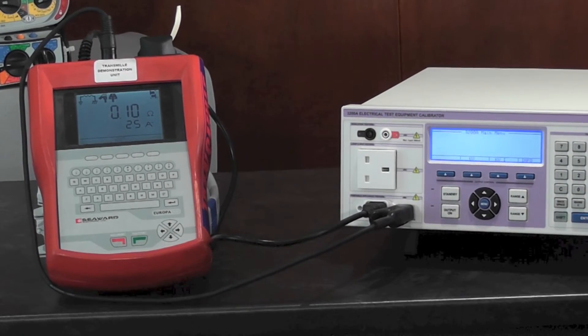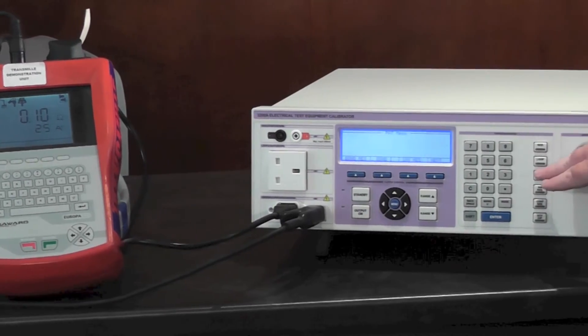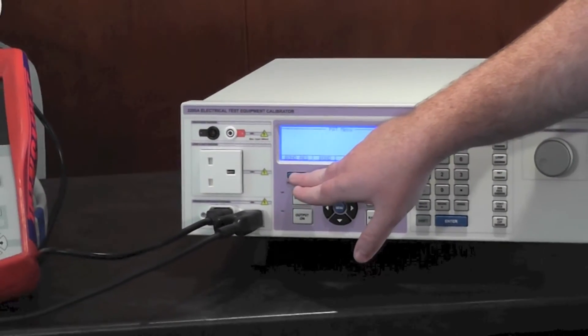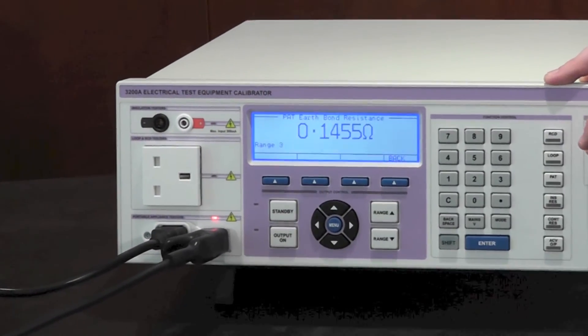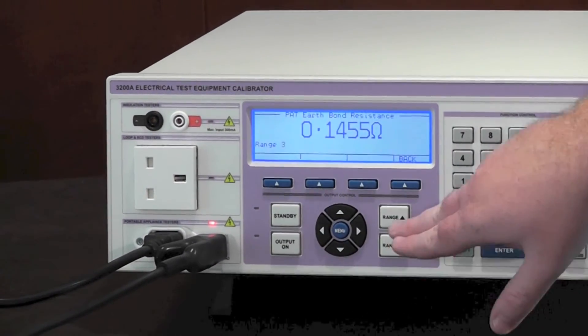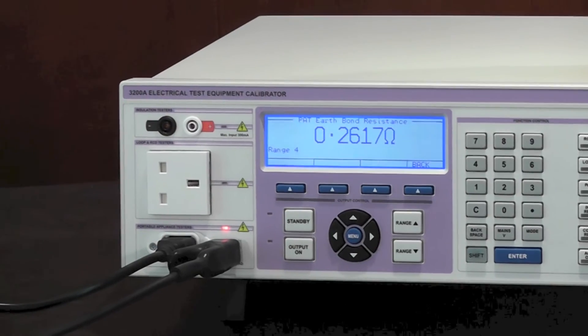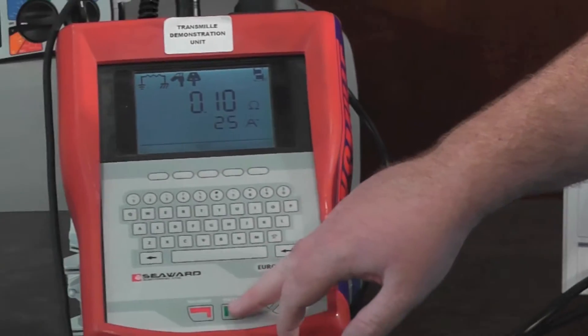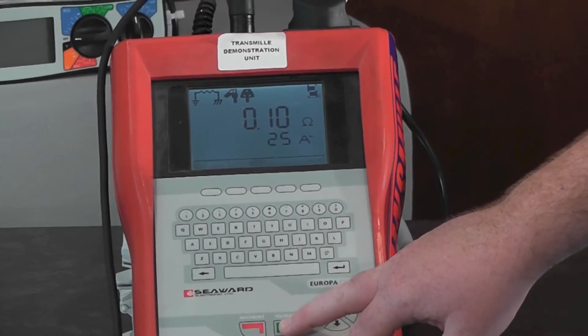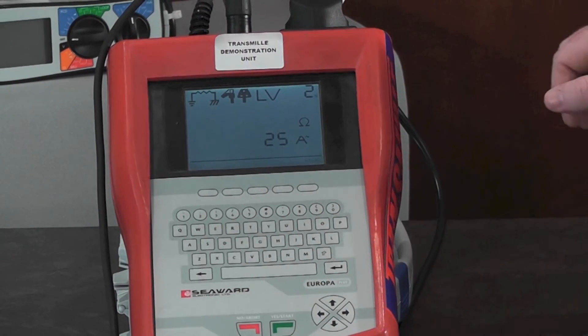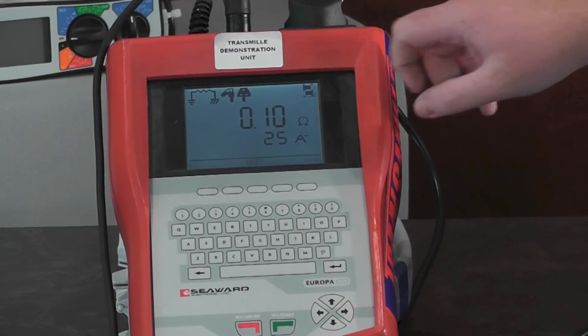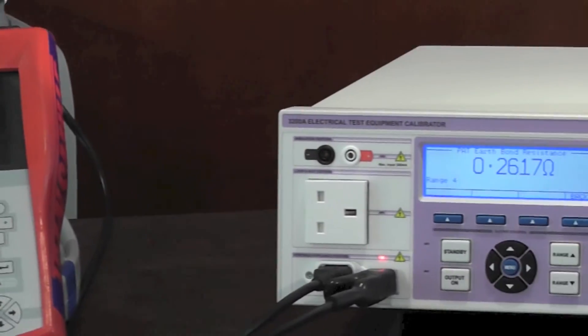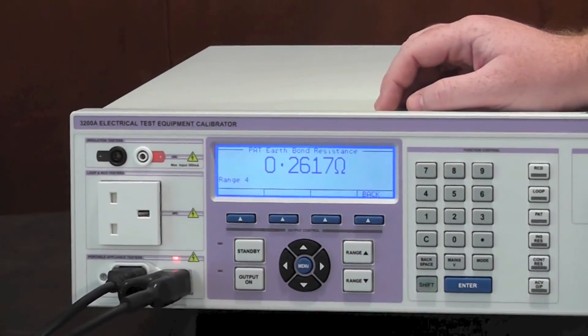I will now enter the PAT mode, select bond resistance as required, select the range using the digital control or the range up and down keys and then press test on the tester. You will then compare the indicated result from the PAT tester against the supplied result from the 3200A.